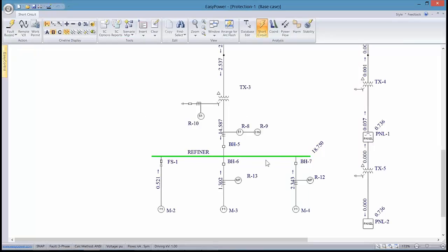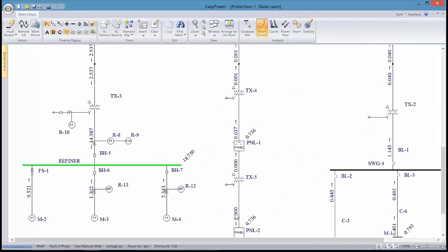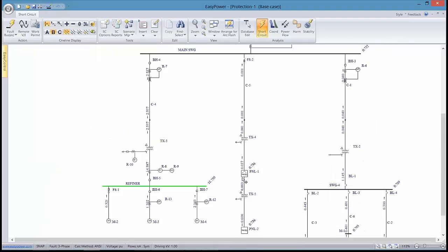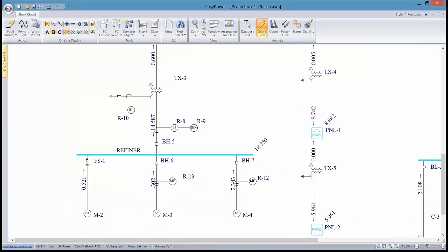We see the direct short circuit currents, but now we also see the contribution of branch currents from any remote bus and the effect on its voltage. Whereas on this particular bus, we're showing current on the oblique. On the remotes, we're showing voltage, and this is per unit.